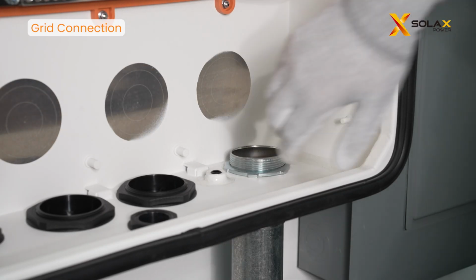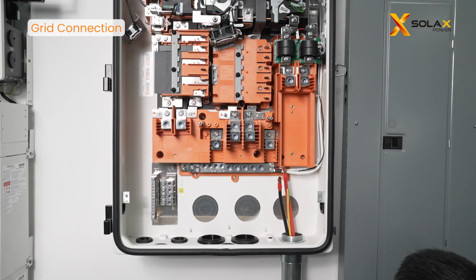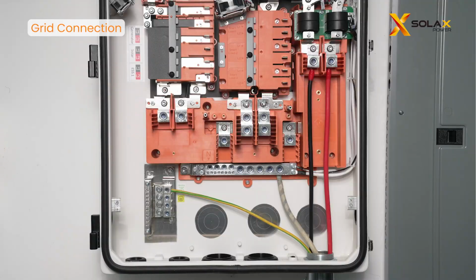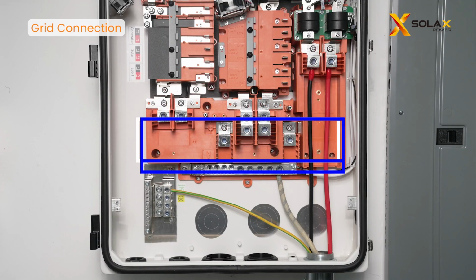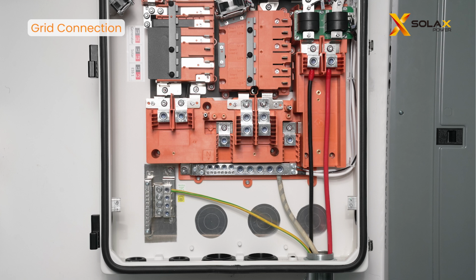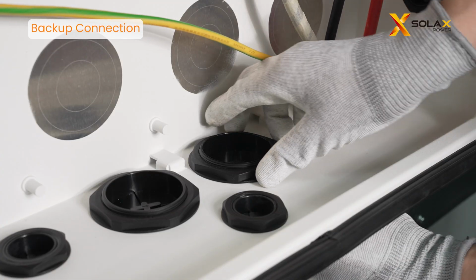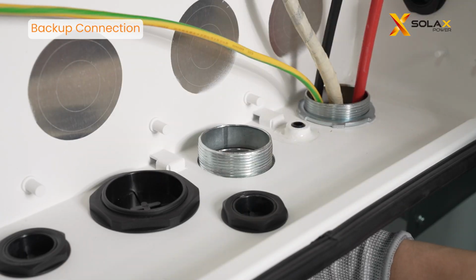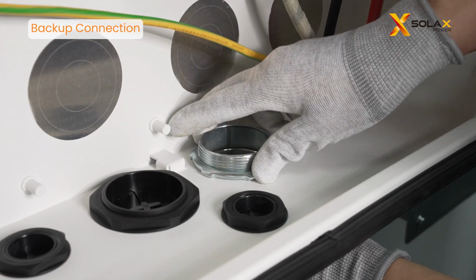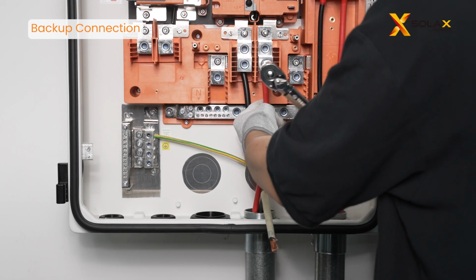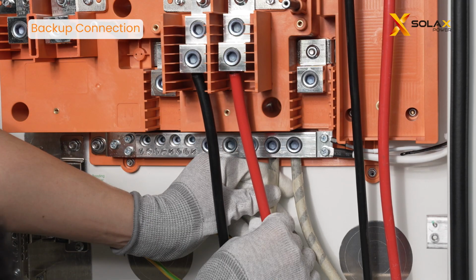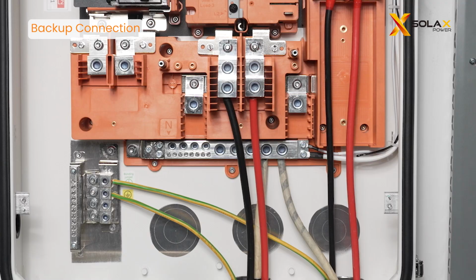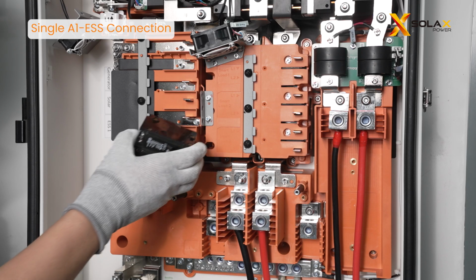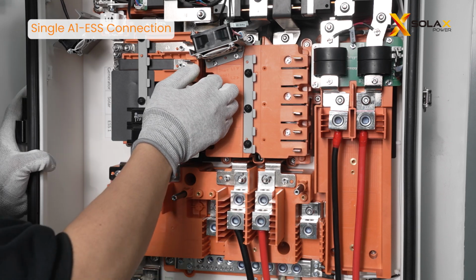Unscrew the waterproof plug and install the waterproof pipe. Insert the grid cables into the pipe and grid ports, and fix them. Unscrew the waterproof plug and install the waterproof pipe. Pass the backup cables through the pipe, and connect them to backup ports. Install the branch circuit breaker.